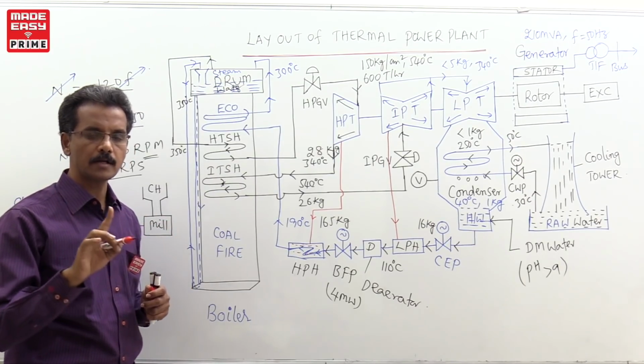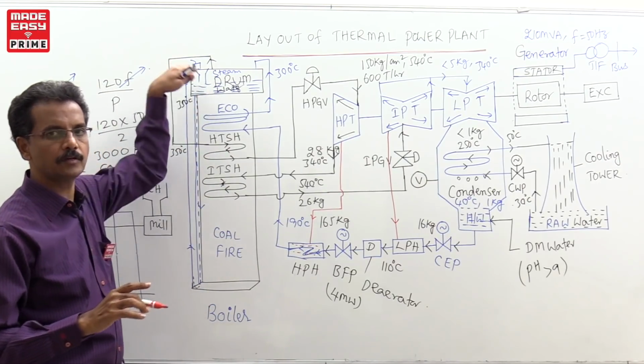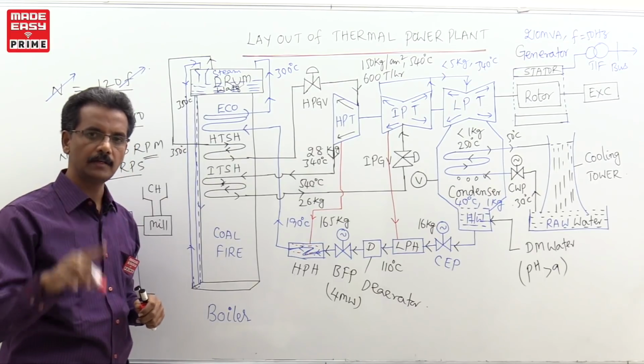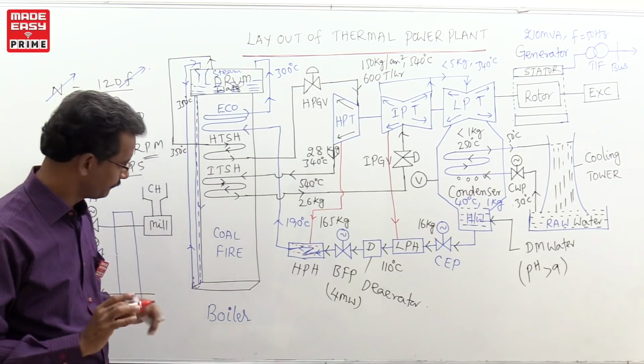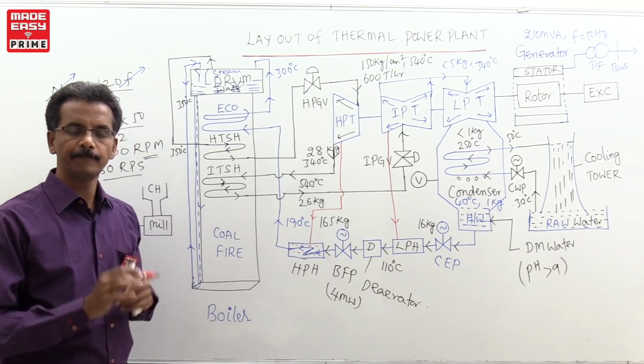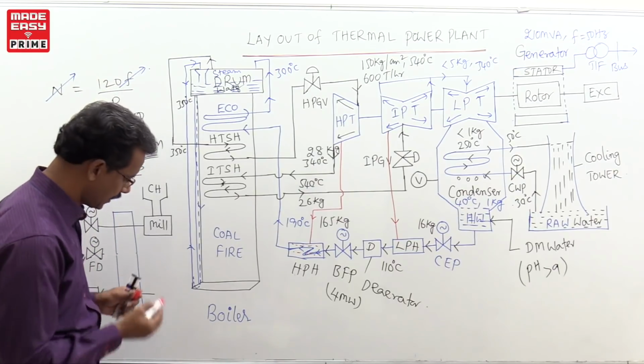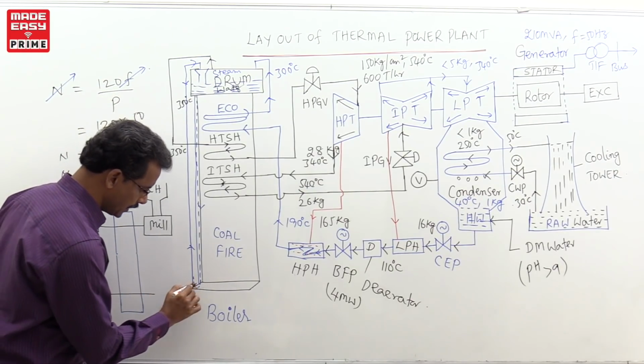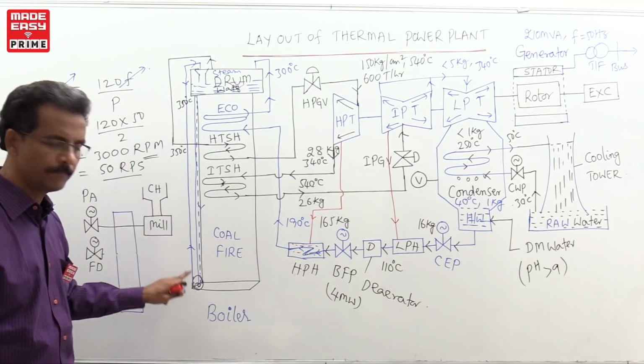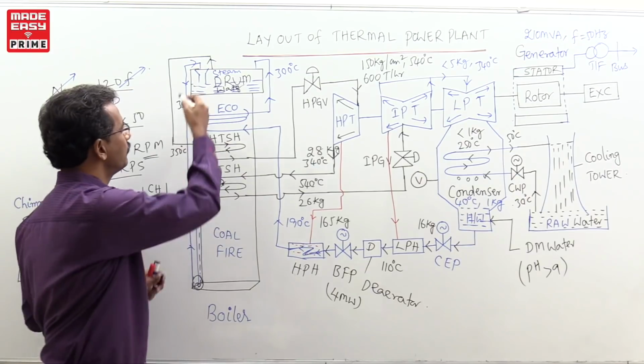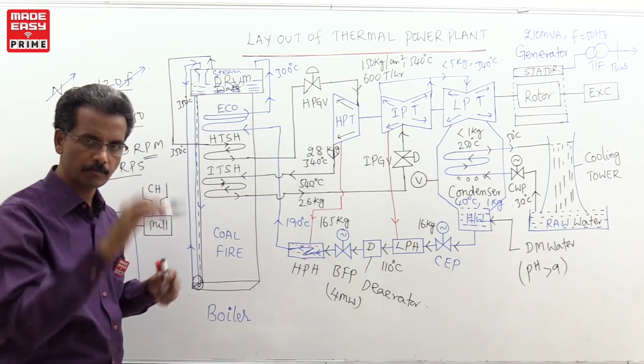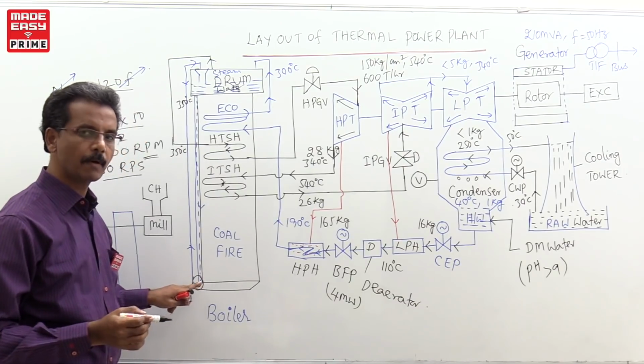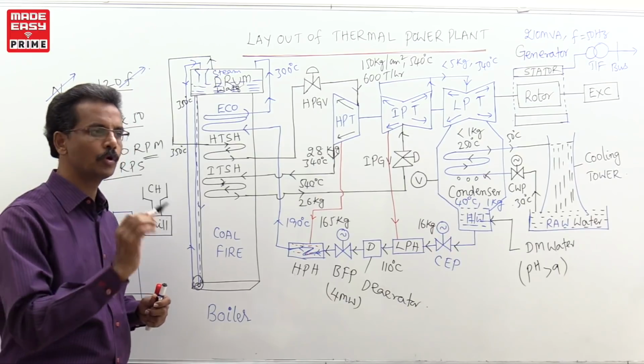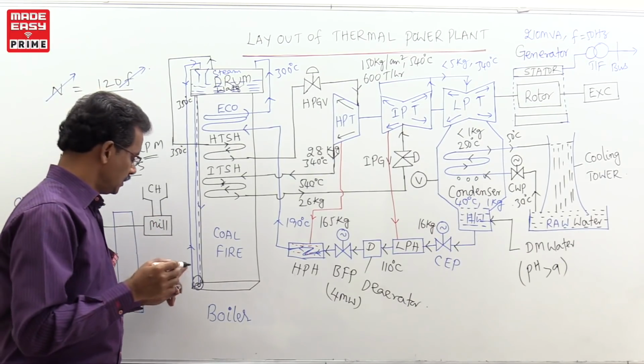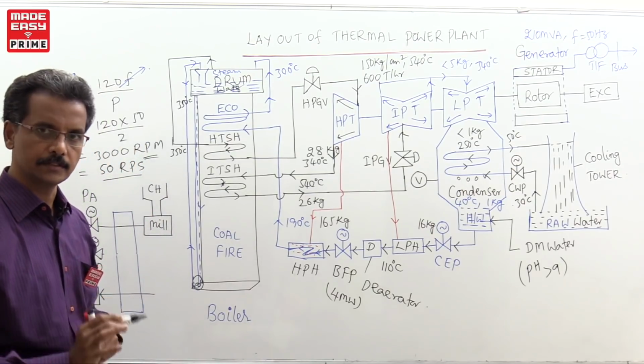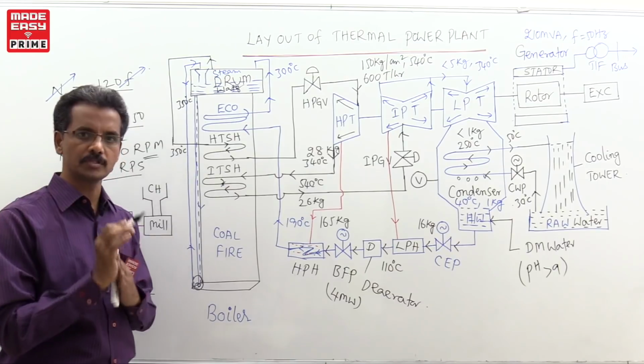Natural circulation means water from the drum to the boiler and once again to the drum will circulate naturally without using any pump, right? This is used in less than 500 MVA generator capacities. If you are using more than 500 MVA generator capacities, one more pump is added. This pump is used for circulating water and steam from the drum to the boiler and back to the drum. Okay, so this extra pump is used in the case of more than 500 MVA capacity generators. That is what is called forced circulation. Okay, you should think of natural circulation versus forced circulation, what is the meaning of forced circulation, right?